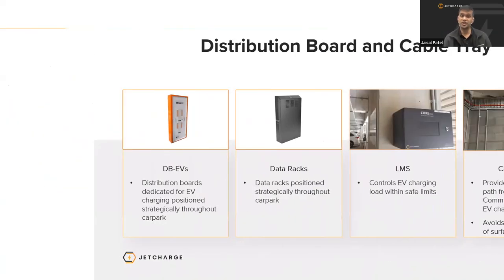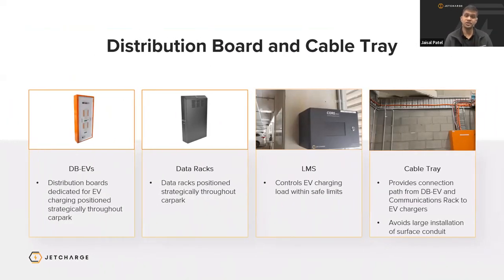In terms of provisioning, what do we typically allow for? Distribution boards, we have two methods, a distribution board and cable tray method and a busway method. With the distribution board and cable tray method, we have a centralized distribution board located somewhere in the car park, essentially trying to be as central to the entire car park as possible. We like to locate them on every level in the core of the car park, essentially, so that we have the shortest possible cable runs from the chargers back to the distribution board.